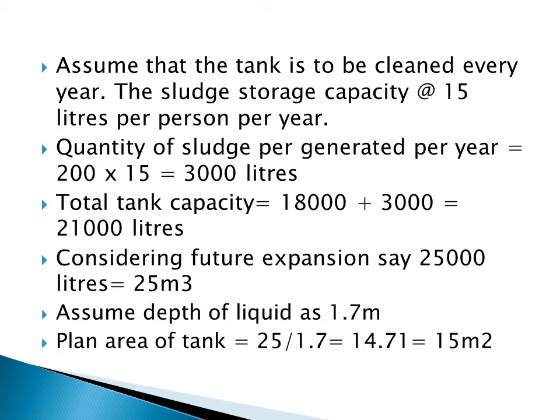We assume the tank is cleaned every year. The sludge storage capacity is assumed as 15 liters per person per year. If not given, you can assume a value between 15 to 30 liters per person per year. The quantity of sludge generated per year is 200 multiplied by 15, which equals 3,000 liters. To the tank capacity of 18,000 liters, you have to add these 3,000 liters for sludge deposition.